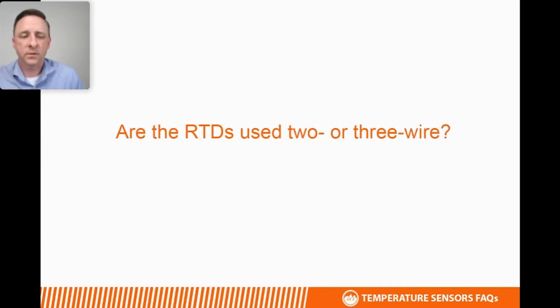Are the RTDs used 2-wire or 3-wire? All of our devices are 2-wire. Our temperature transmitter boards can accept a 3-wire RTD input, so you can use our boards with RTDs that you may already have in the field. Typically on a 3-wire RTD, you're going to have 2 wires that are the same color and 1 wire that's a different color. You would just tie those 2 like-colored wires together into one side of the terminal block on our transmitter boards.